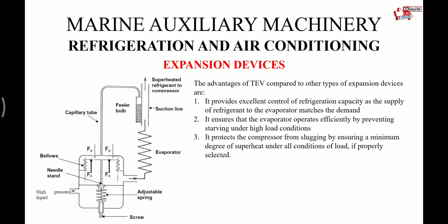If this expansion valve is properly selected, it does not allow any liquid refrigerant to enter into the compressor, as this can form sludge with the lube oil or damage the bearing, and can also damage the cylinder head and the cylinder, as this liquid refrigerant is non-compressible.